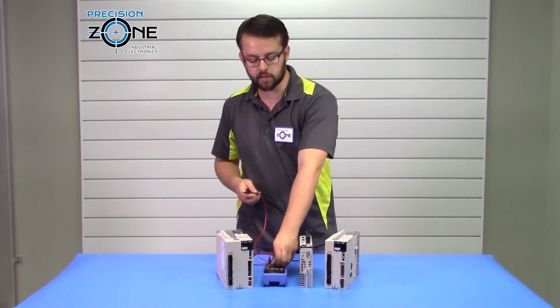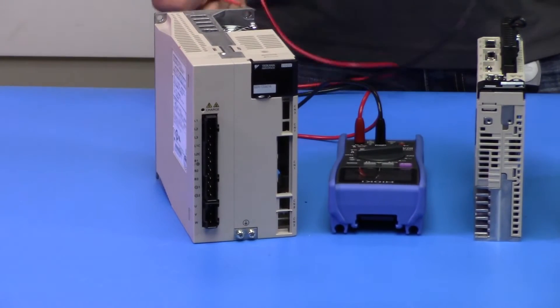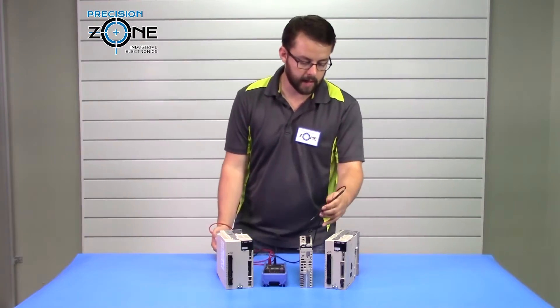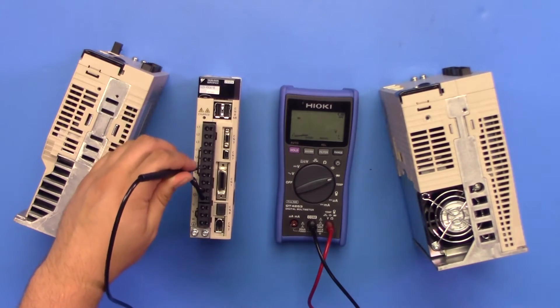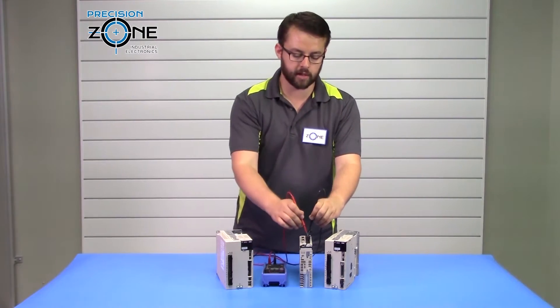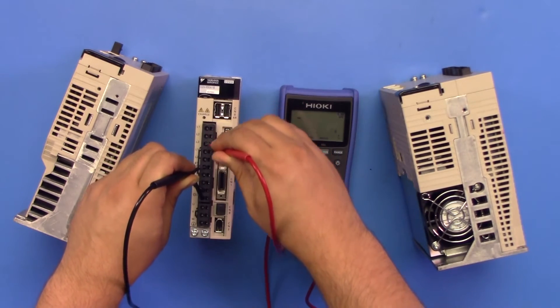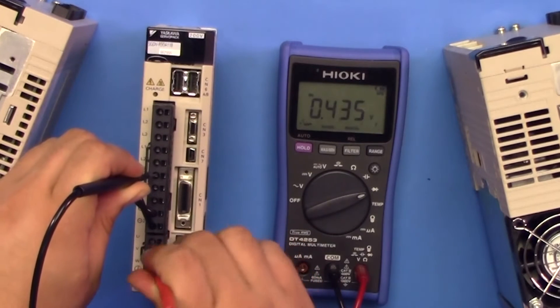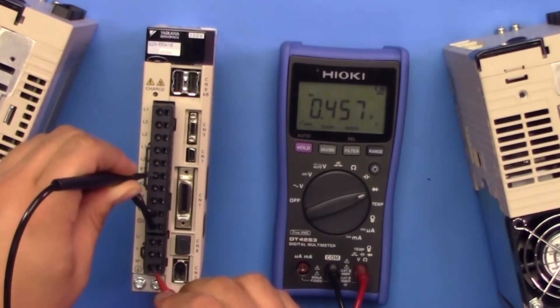So to begin, you want to set your digital multimeter to the diode test function. You want to get the negative side of the digital multimeter and connect that to the positive side of the DC bus, which would be at B1. And you're going to want to check your inputs at L1, L2, and L3, which should be about 0.48 volts. You then want to check your outputs at UVW. That's going to be about 0.43 volts, and that should be normal.